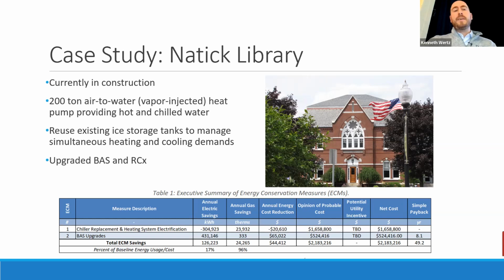So Natick Library, that project's in construction right now. They had an air-cooled chiller that was on its last legs, and it had four compressors and maybe two of them were left running. So we designed this one. We went with the air-to-water heat pump that can make chilled water or hot water. We took out the air-cooled chiller, put the new heat pump in its same place, fit on the same steel, et cetera, on the roof.